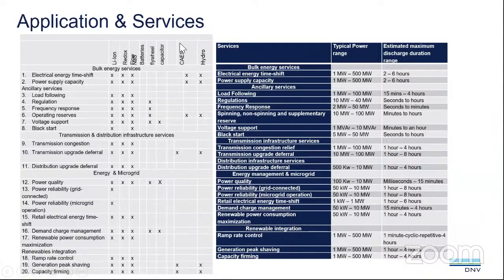Apart from that, ancillary services is a place where battery finds application - charging, discharging following the load curve, used for primary response and giving synthetic inertia for frequency response. They can support secondary reserves and spinning reserves, support voltages whenever required, and even charge a dead bus, hence used for battery black start.